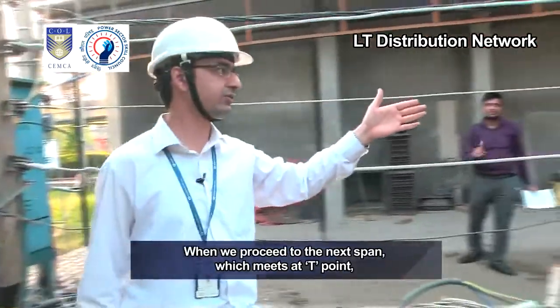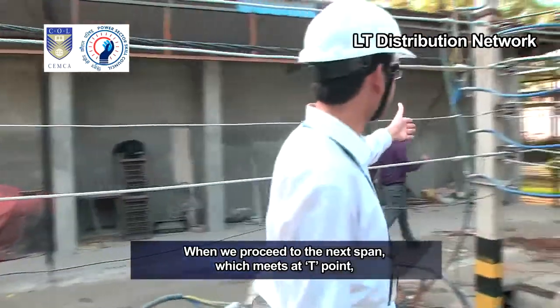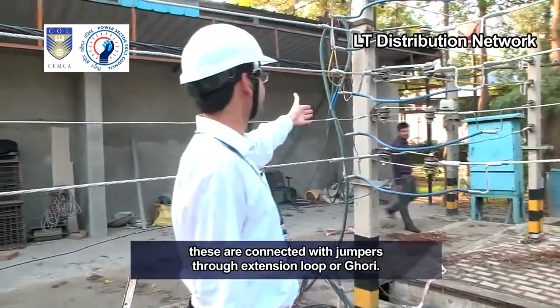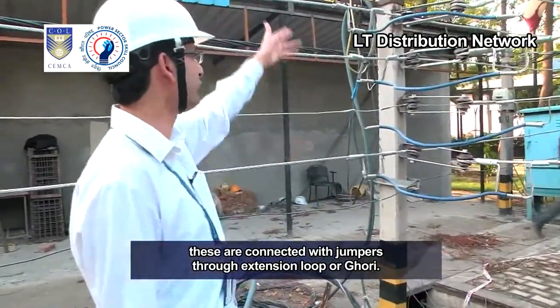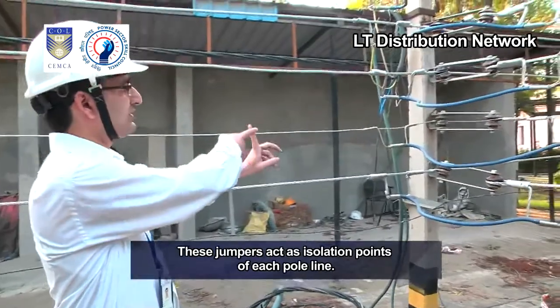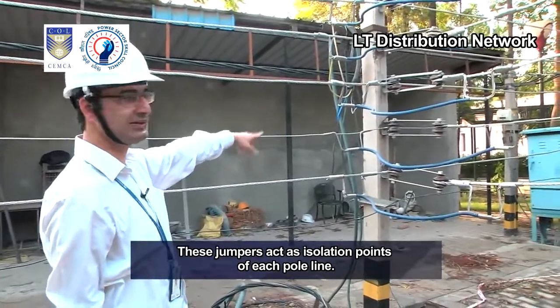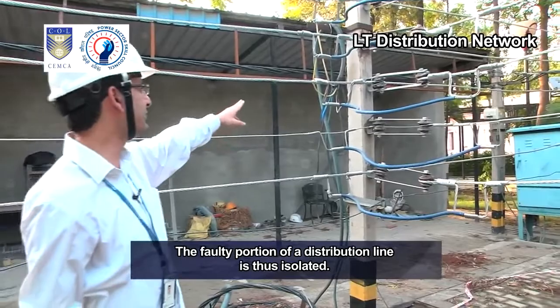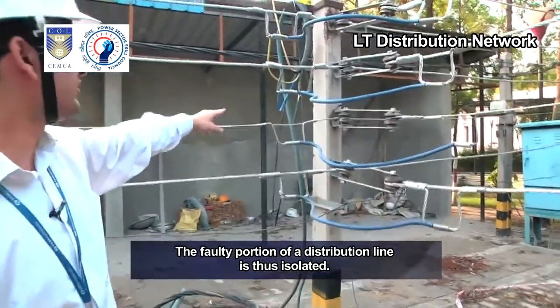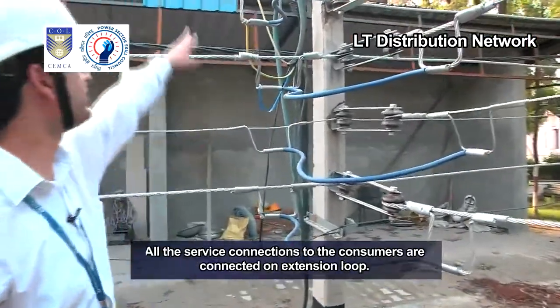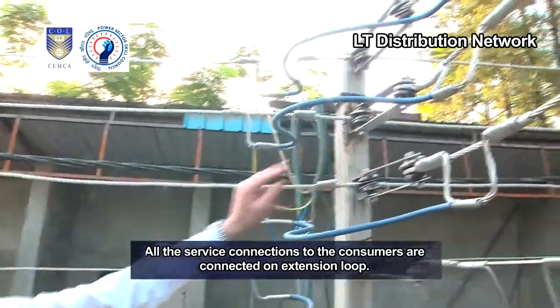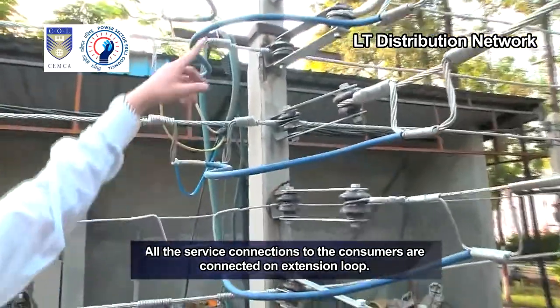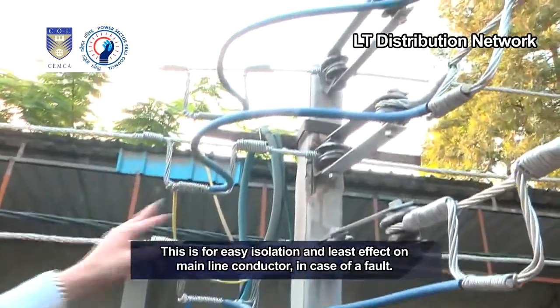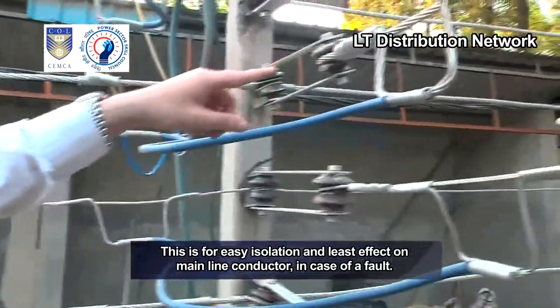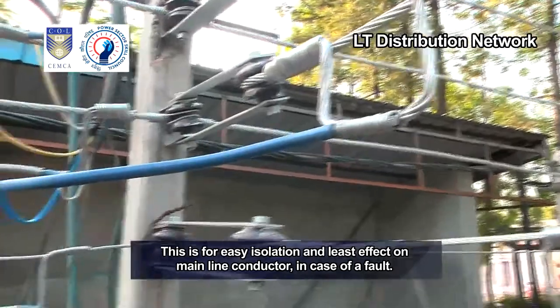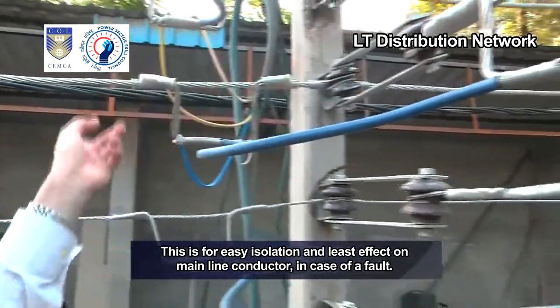When we proceed to the next span, which meets at T point, these are connected with jumpers through extension loop or ghori. These jumpers act as isolation points of each pole line. The faulty portion of a distribution line is thus isolated. All the service connections to the consumers are connected on extension loop. This is for easy isolation and least effect on main line conductor in case of a fault.